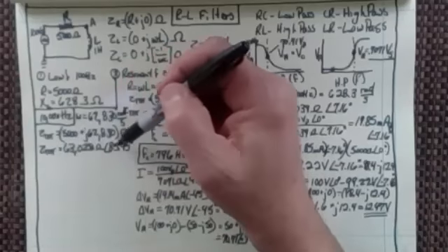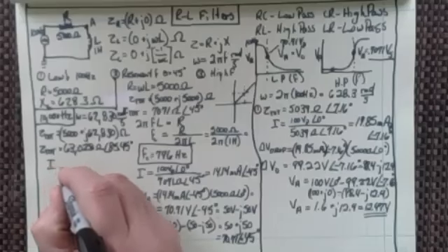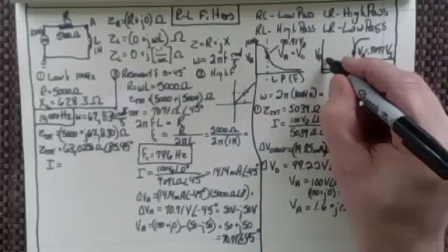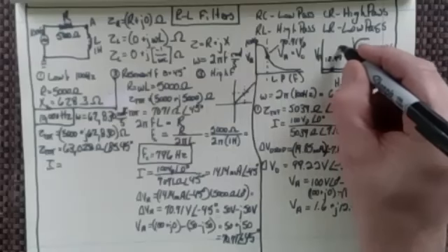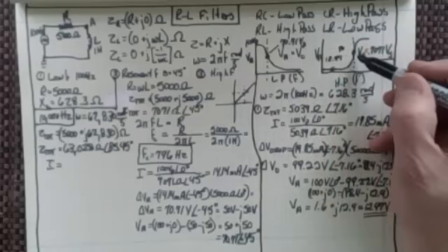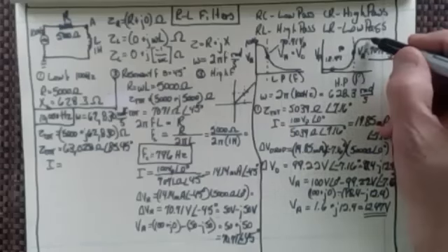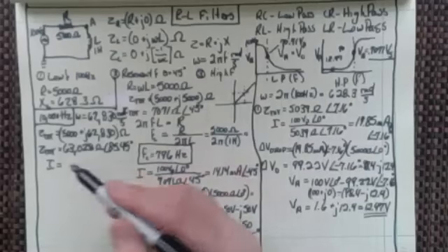So 63,000 at 85.45 degrees, then we can get our current, and I think everybody can see our current is going to be almost zero, right? So this one down here, that was like 12.47. Then here was 70.71 right there. They call these fine point. This is not a fine point. And then up here, we want to see what that is too. And so we've got the total.